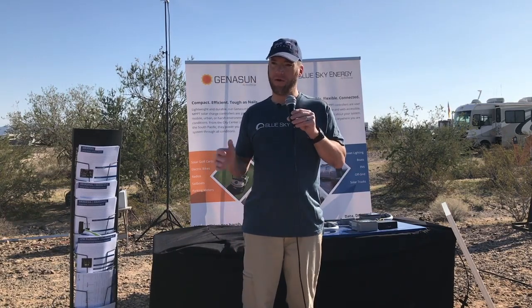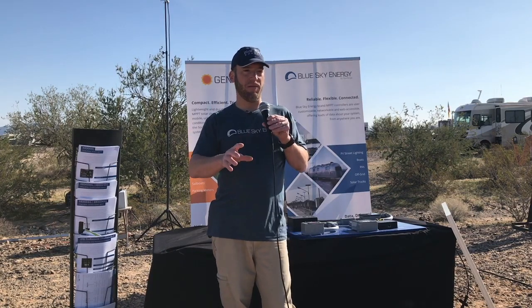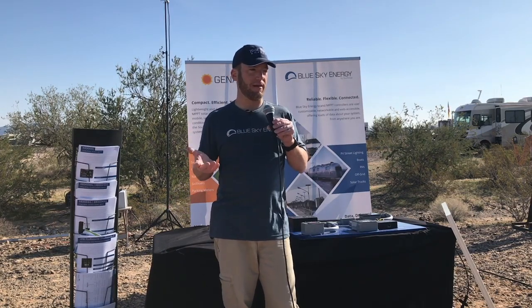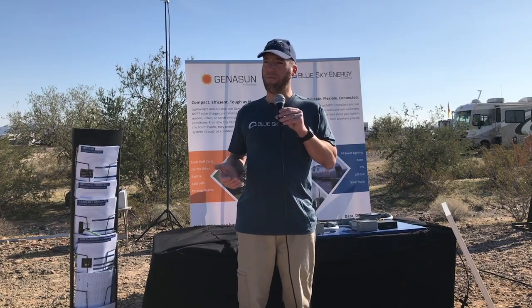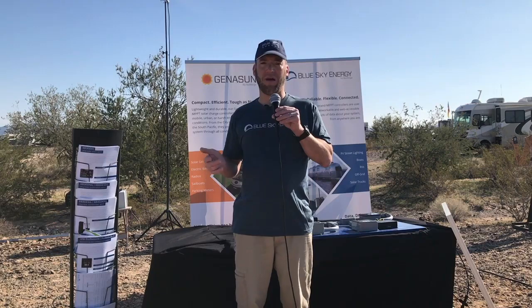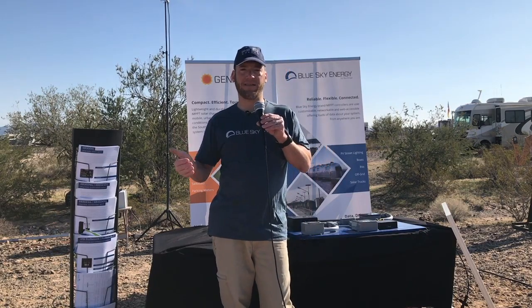Now same thing, when you equalize your batteries, you are using some of that secret sauce from your plates, but you're also keeping the sulfation off the plates. As a rule of thumb, as an industry standard, you pretty much say you equalize for 2 hours every 30 days if you're actively cycling your batteries.